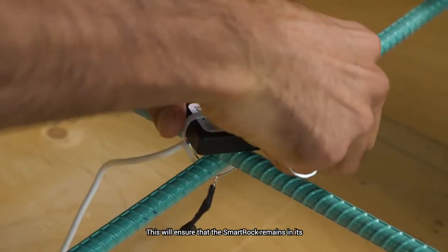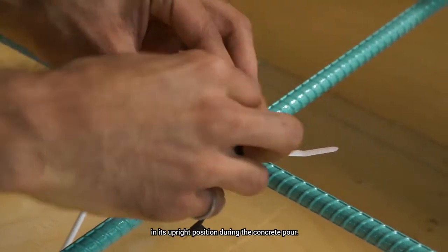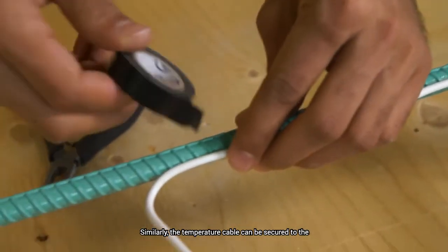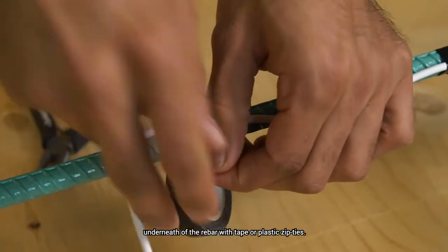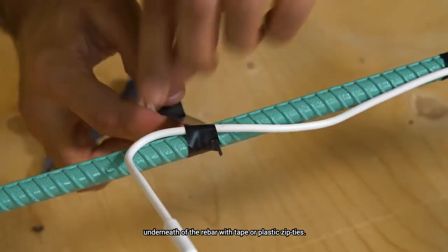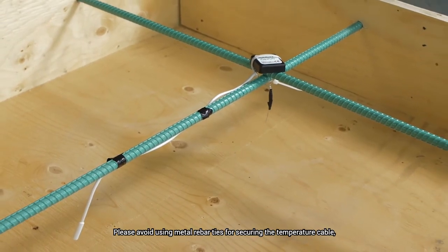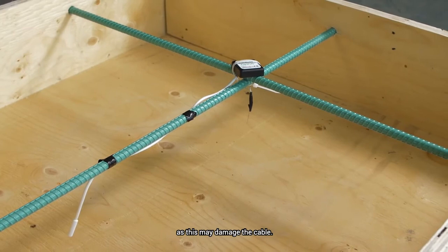Similarly, the temperature cable can be secured to the underneath of the rebar with tape or plastic zip ties. Please avoid using metal rebar ties for securing the temperature cable, as this may damage the cable.